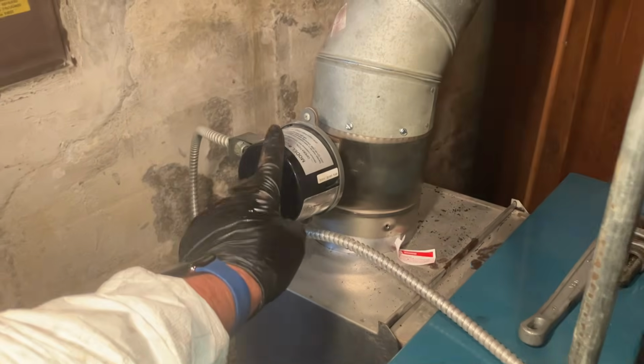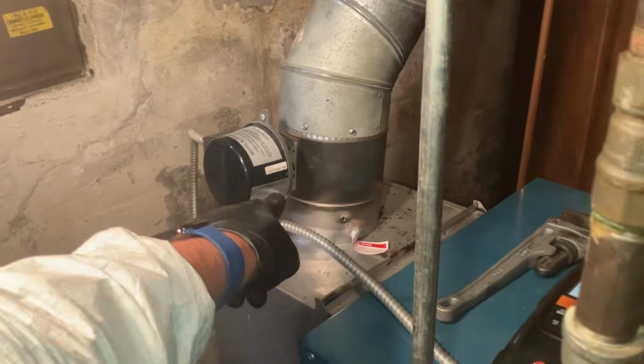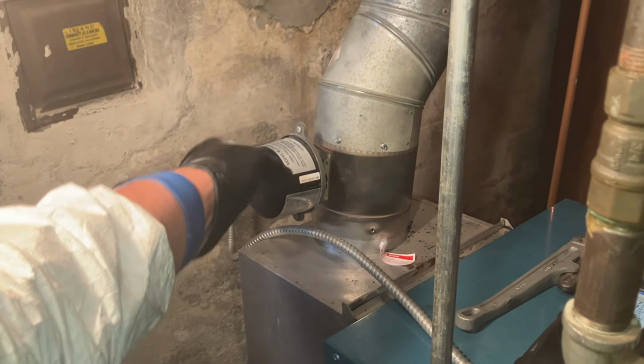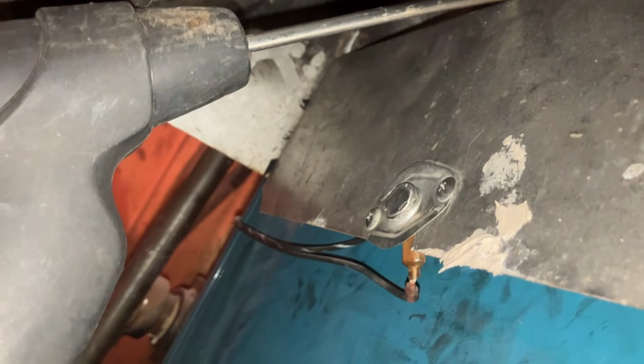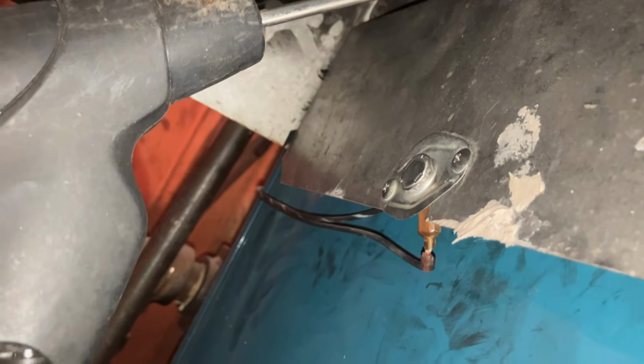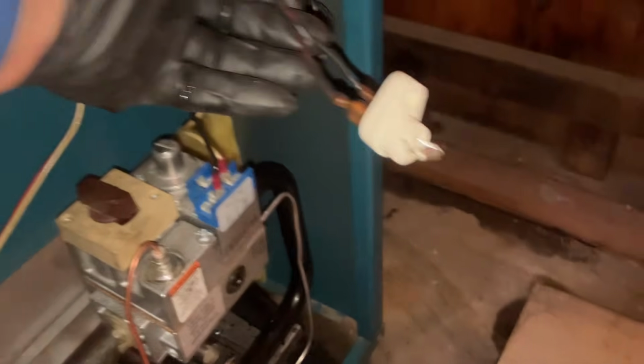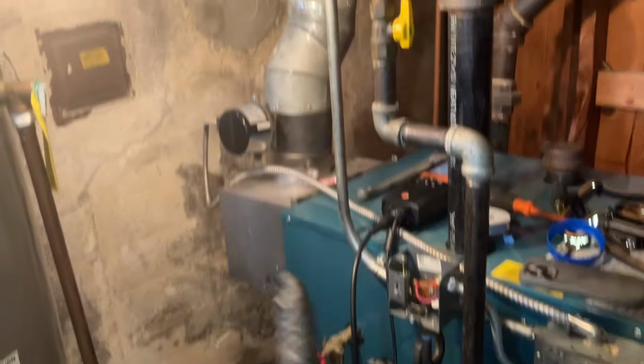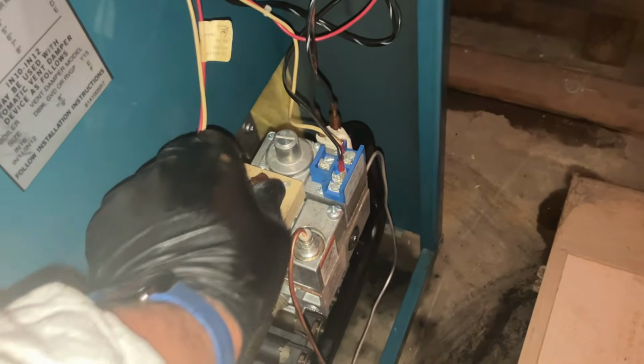We have an automatic vent damper that has an end switch that will close the circuit if the damper is open. We have a spill switch right there that as long as it's not out on safety, the circuit is closed. We also have a rollout switch right there. For testing purposes, I'm leaving it there for now. And as long as 1, 2, 3, 4, 5 safeties are all closed, we will get power to our gas valve. So let's turn our gas valve from pilot to on.